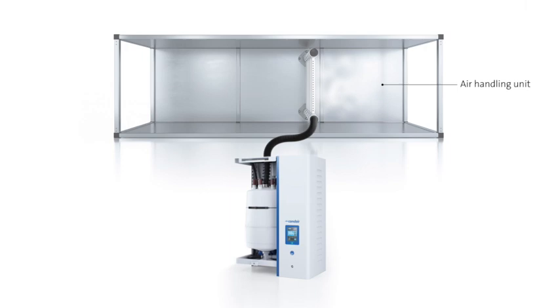Well, one of the first decisions that needs to be made is whether you're going to introduce humidity directly to a room's atmosphere or put it into a building's air handling unit, often referred to as an AHU. Now, if a building has an AHU, the simplest option can be to fit the humidifier there. But many buildings and factories don't have this. They don't have an AHU. So humidifiers can be installed directly in a room, or at least close to the area in question, with a duct feeding the humid air to where it's needed.